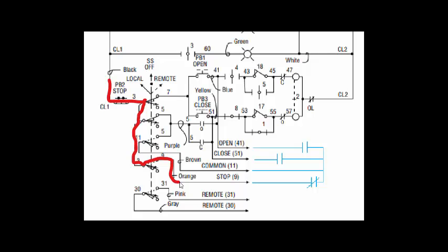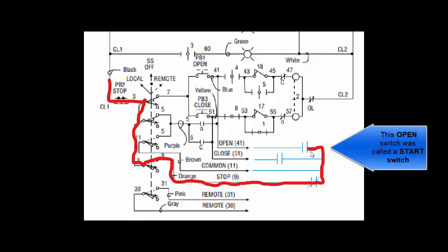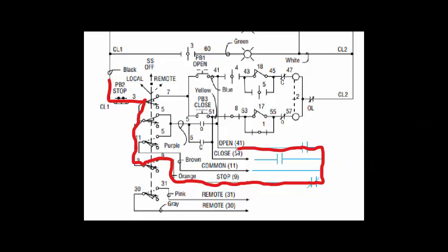When we're in remote that brings voltage out on this orange conductor to the normally closed remote stop switch. Assuming that switch is not pressed, contact is made up, the voltage is able to go up to the start switch.